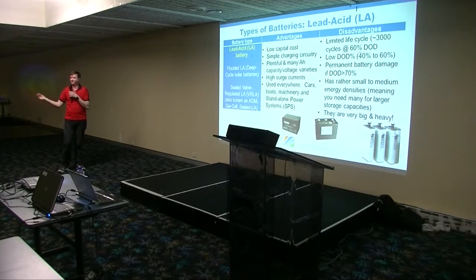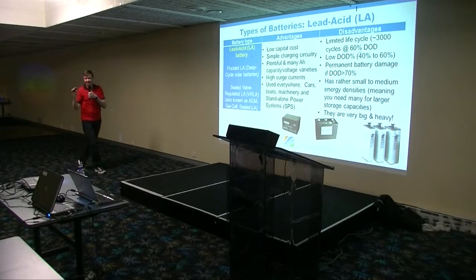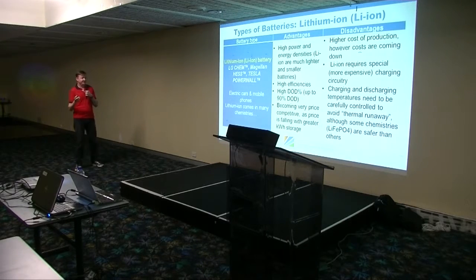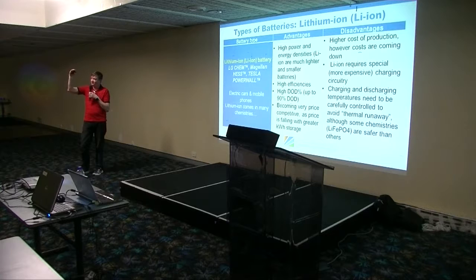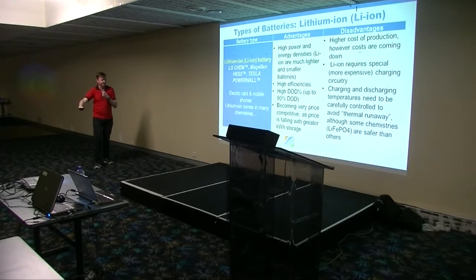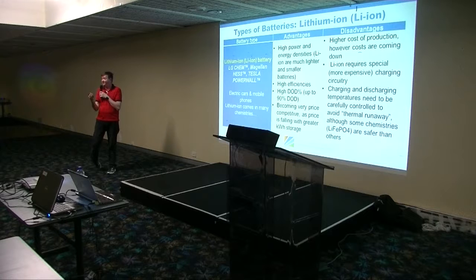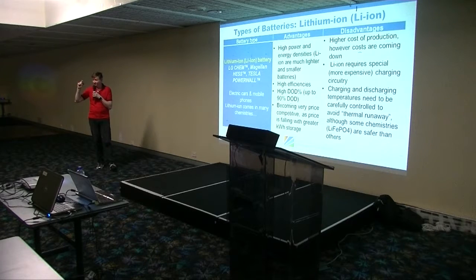Without destroying the battery, it has limitations in its use. Lithium ion, on the other hand, has a much deeper depth of discharge. That means if the battery was full, you can drain it all the way, in this case, to 90% of its energy, leaving only 10% left. So you've got almost all the energy in that battery you can use. That's fantastic, because with lead acid it's only about 20 to 30% you can use, but this one you can use 90% of it.